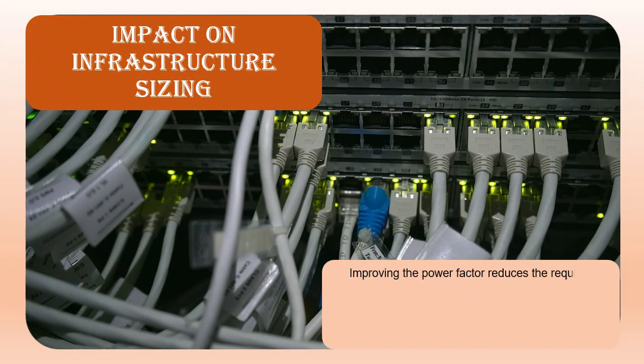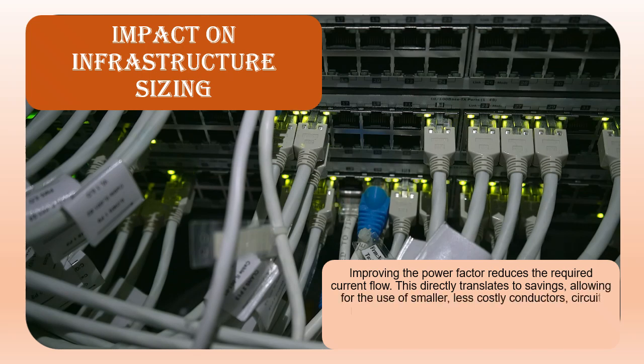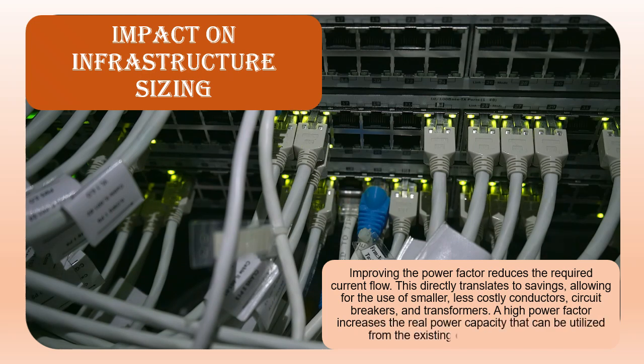Impact on infrastructure sizing. Improving the power factor reduces the required current flow. This directly translates to savings, allowing for the use of smaller, less costly conductors, circuit breakers, and transformers. A high power factor increases the real power capacity that can be utilized from the existing electrical infrastructure.